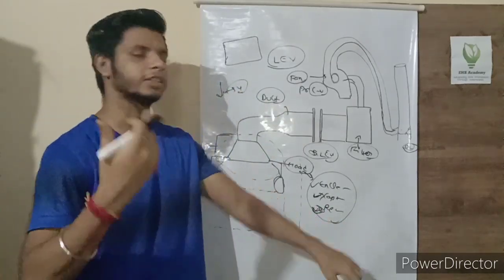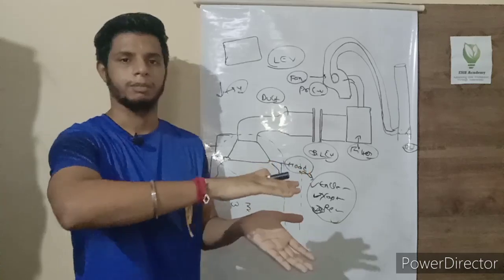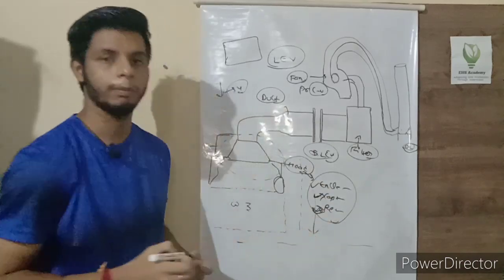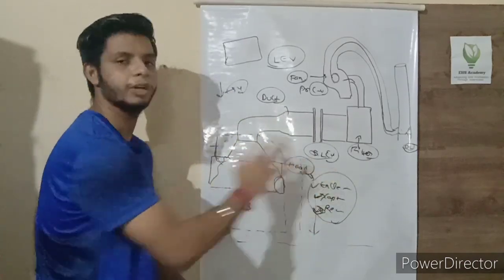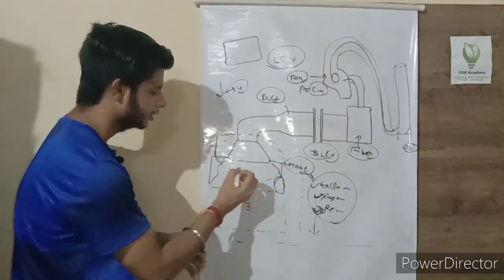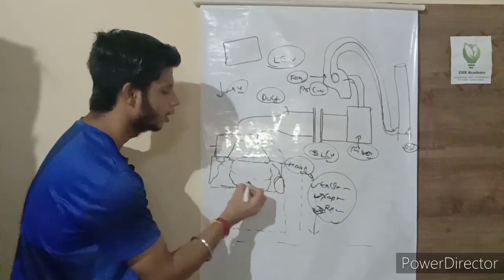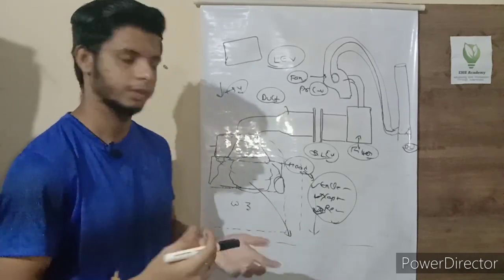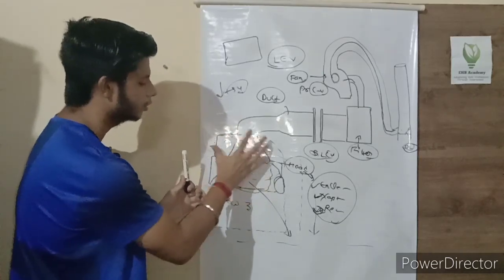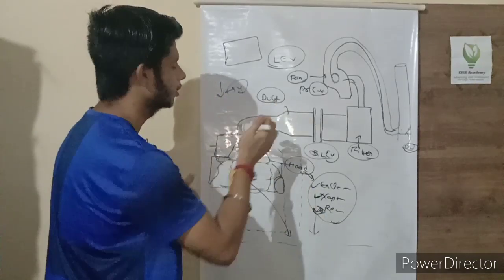A capturing hood is fixed at a static position — it will not move from its intended location; you bring your work to it. A receiving hood (also called a recapturing hood) can be moved in any direction based on your work — for example, moved to floor level if needed. The hood collects whatever contaminant cloud is generated at the workstation. You can visualize the cloud movement using a Tyndall lamp to check how effectively the hood is capturing contaminants.